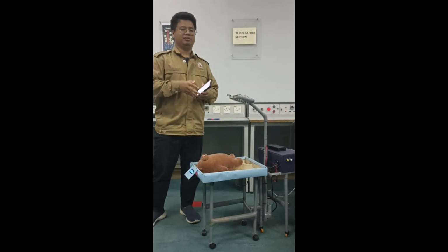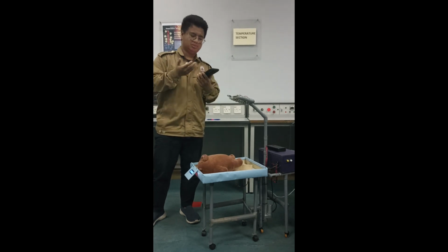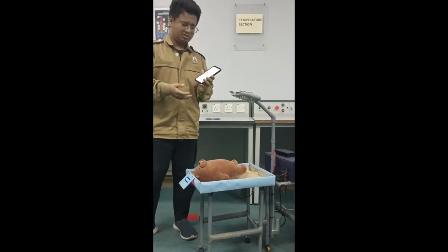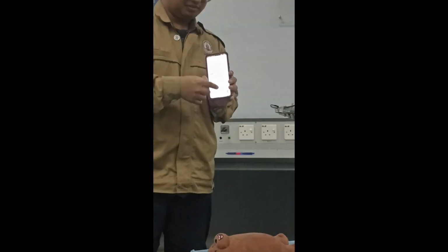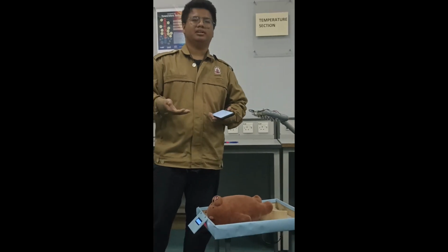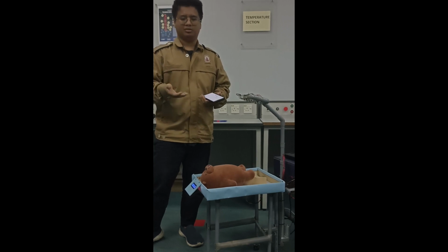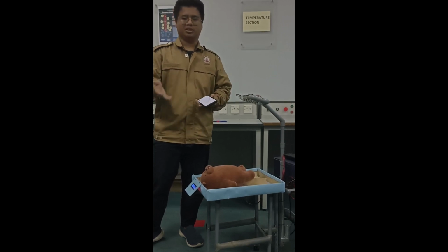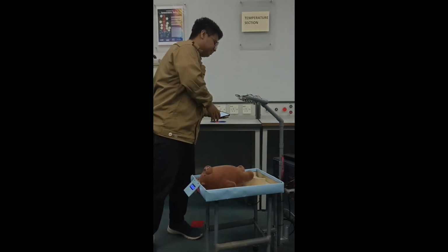We use Blynk to control, which can control up and down. We can also monitor the data, which shows the distance value and irradiance value. The irradiance value lets the user know how long the baby with jaundice should be treated.